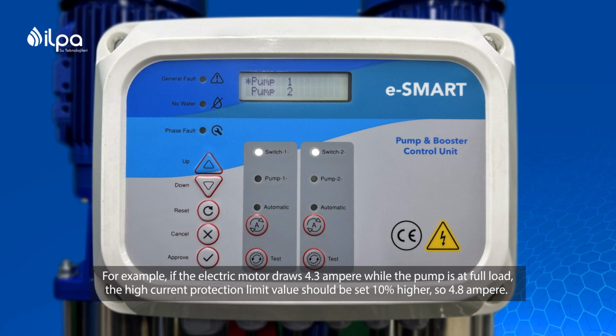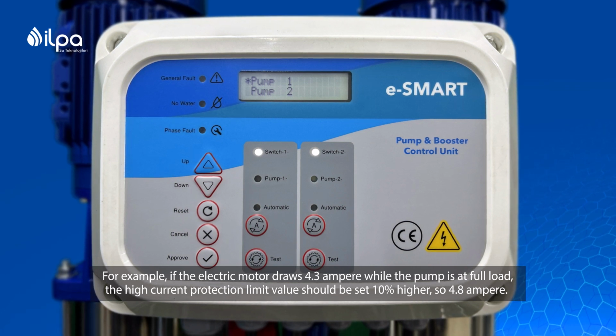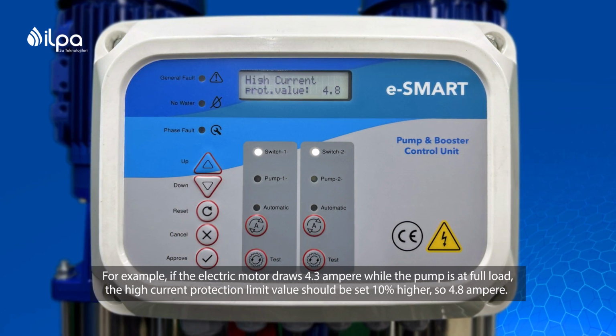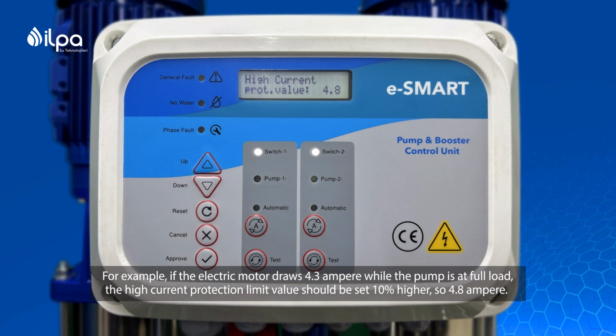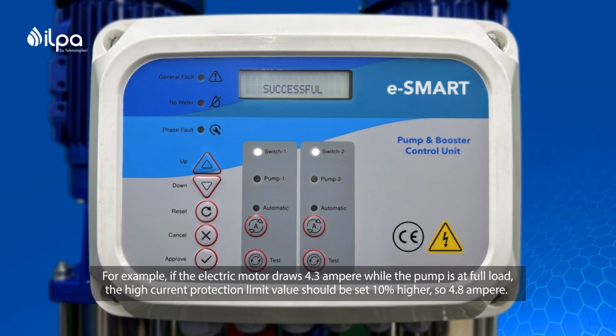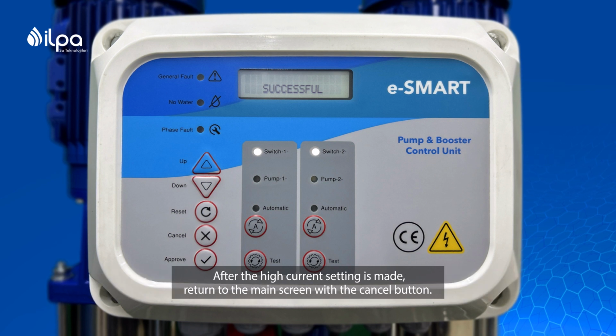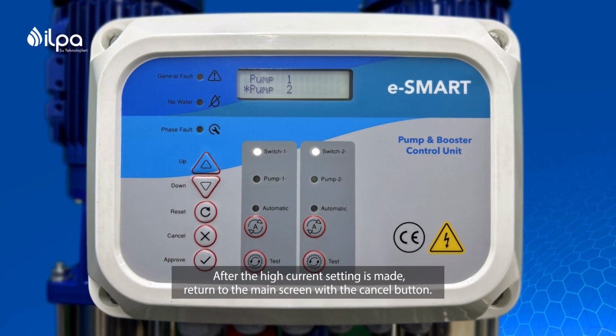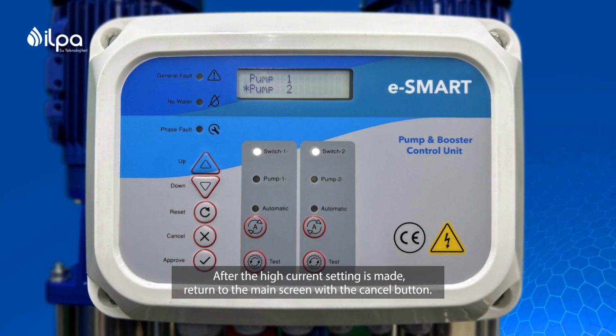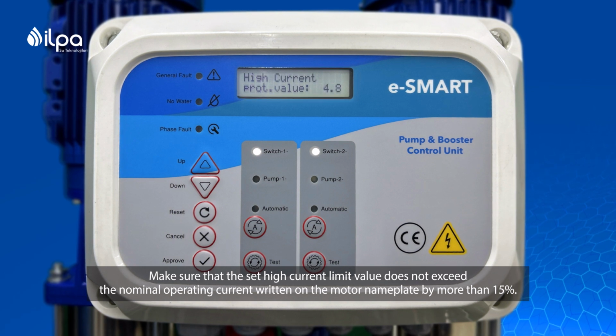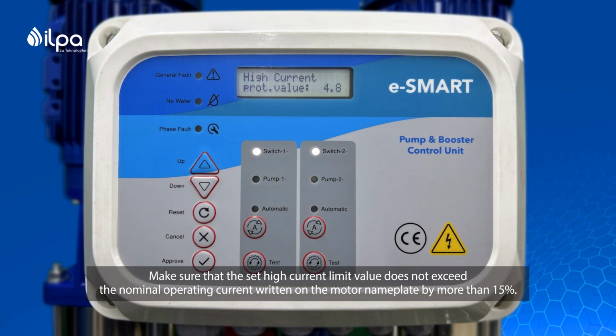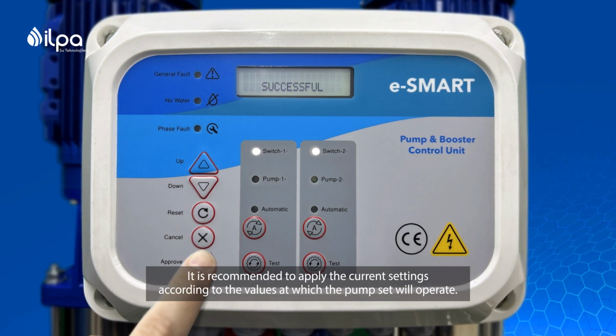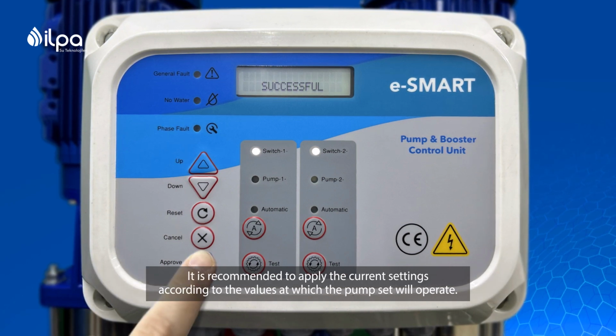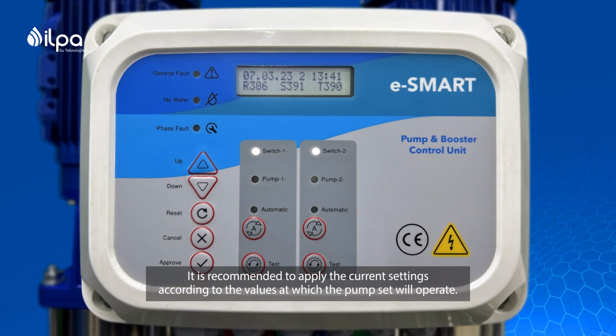For example, if the electric motor draws 4.3 ampere while the pump is at full load, the high current protection limit value should be set 10% higher, so 4.8 ampere. After the high current setting is made, return to the main screen with the Cancel button. Make sure that the set high current limit value does not exceed the nominal operating current written on the motor nameplate by more than 15%. It is recommended to apply the current settings according to the values at which the pump set will operate.